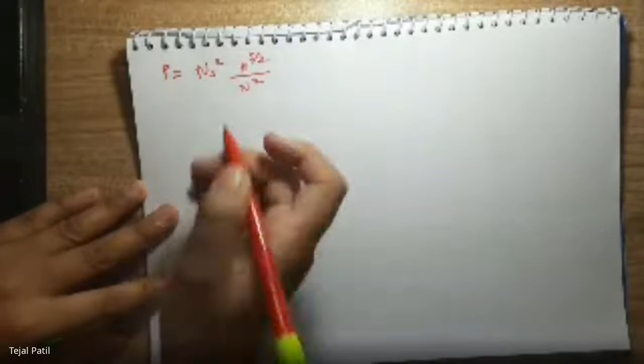Now we have got this equation, right? Now let's find the value for Ns. That is, Ns is equal to, everything will be under root because this is squared, right? So power multiplied by N squared divided by H raised to 5 by 2. Let's take this N out of the under root. And we can write this as N under root of power divided by H raised to 5 by 4. I have taken this as 1 by 2, and you can write it as H raised to 5 by 4. So this is your formula for Ns, the specific speed, keeping in mind that this power should be in kilowatt and head should be in meter.